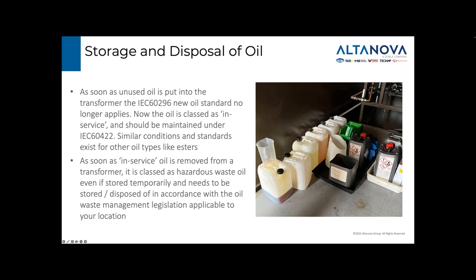Unused mineral oil that we put into our assets is covered under IEC 60296, the new oil specification. Other oil types will have similar unused oil standards. However, as soon as the oil is put into the asset, it becomes classified as in-service oil. The oil now needs maintaining under IEC 60422 or equivalent standard.